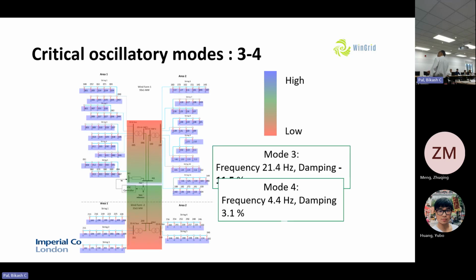But then I go to another one, you see 21 hertz and 4.4 hertz, mode 3 and mode 4, they are now getting spread out. Individual turbines are also participating in this. So compared to type 3, in type 4 now, in type 3 I saw that no individual turbine was contributing to that medium frequency. So that gave me an advantage.